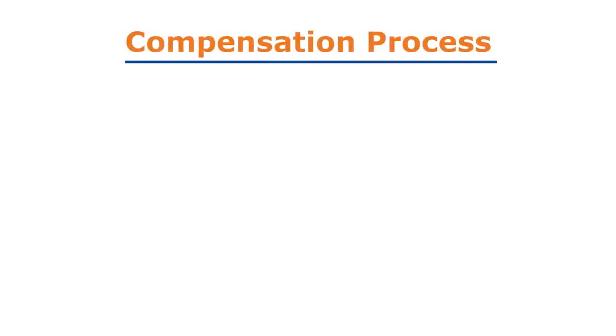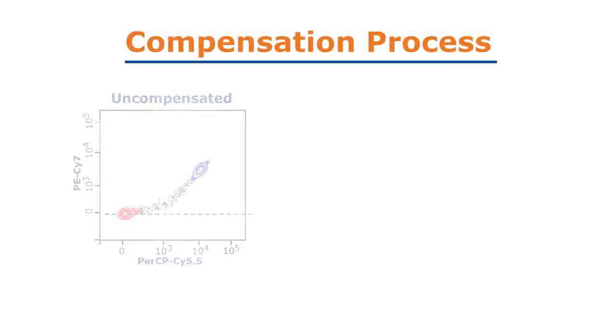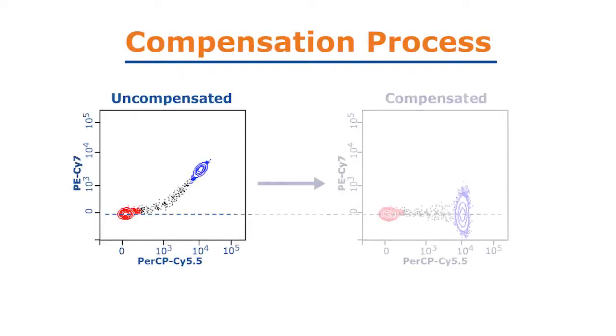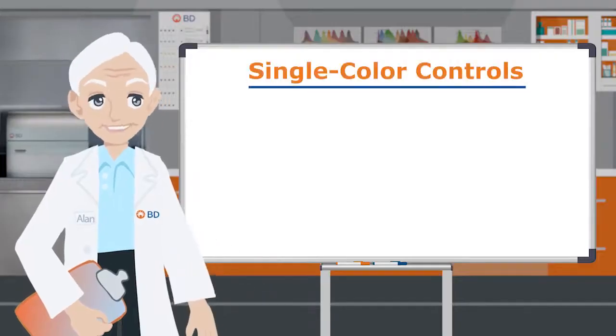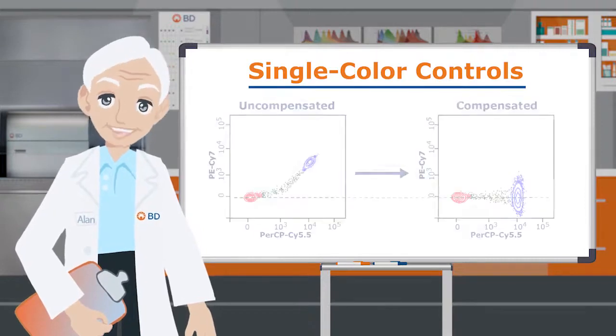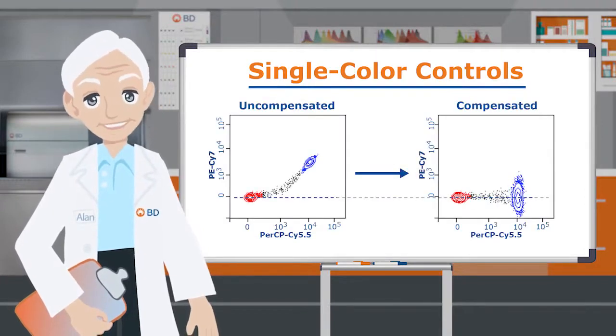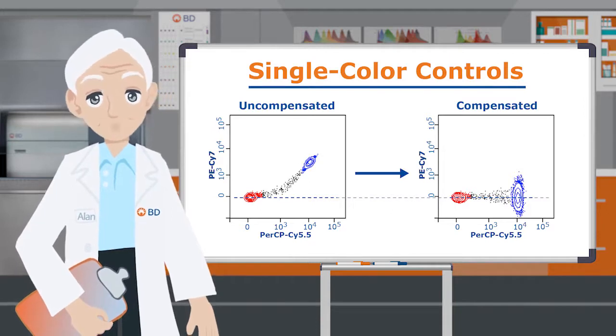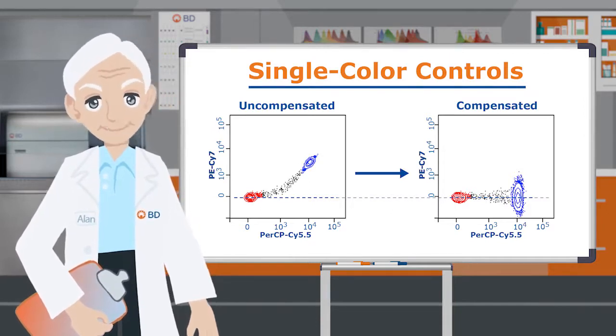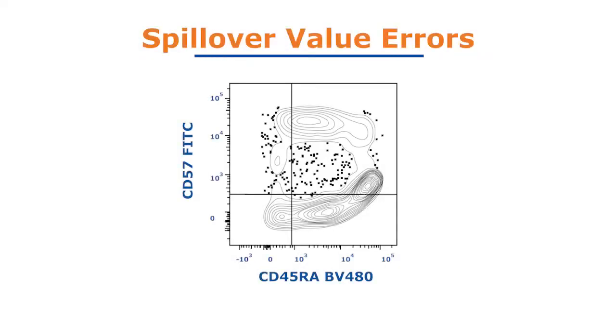In previous videos, we've seen how compensation is the process by which we subtract background due to fluorescence spillover. To perform this compensation, you must run single-color controls. The cytometer software then uses these controls to create a matrix of spillover values and corrects for the background due to spillover. Small errors in calculating spillover values can have major impact on the quality of multicolor assays.